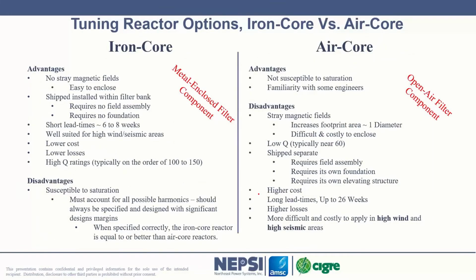So I've shown the difference between iron core and air core reactors here. Again, the advantage of iron core: no stray losses. But a key advantage of air core reactors is that they're not susceptible to saturation. You don't get saturation in an air core reactor. Saturation in an iron core reactor can result in failure.